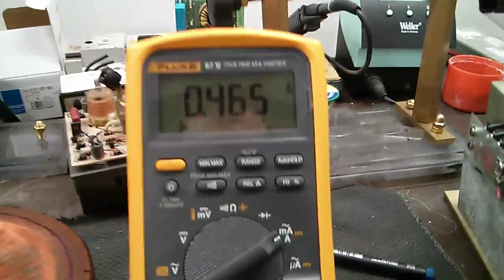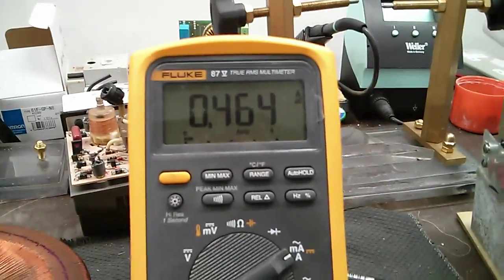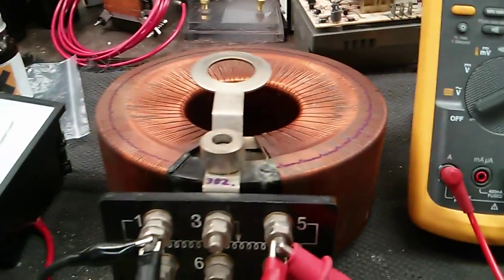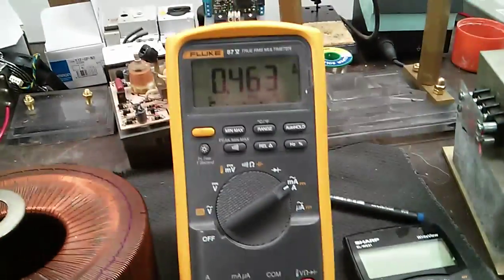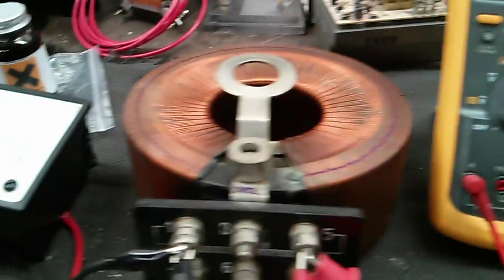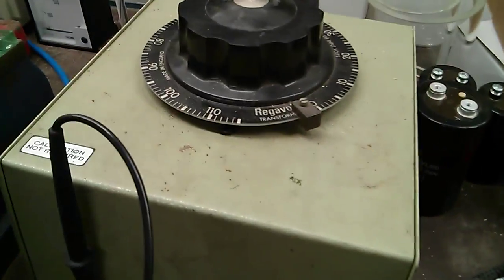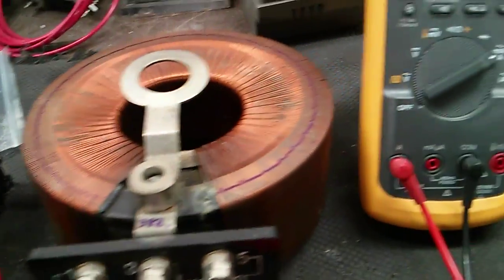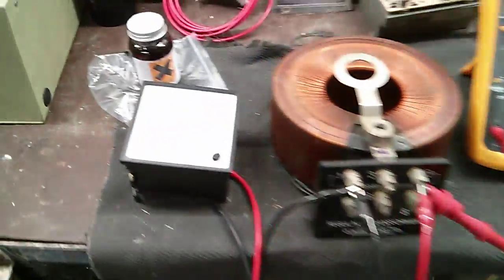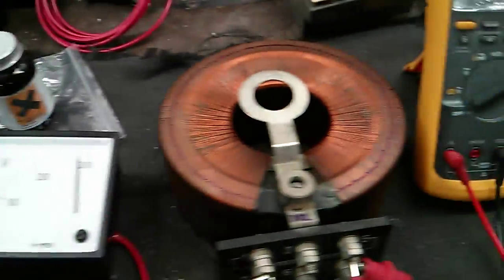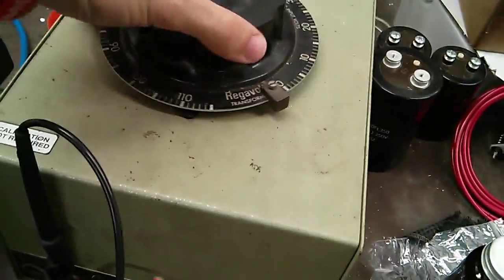So I've taken that to 115 and as you can see it's nearly doubled in actual idle current draw. You can see just by taking it up 15 more percent, the core has slightly saturated and it's pulling nearly twice as many amps. That's just an example of core saturation and how it works.